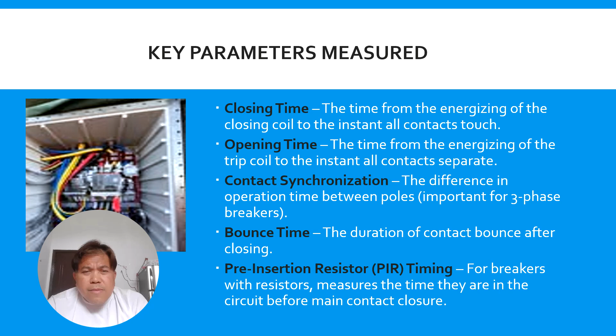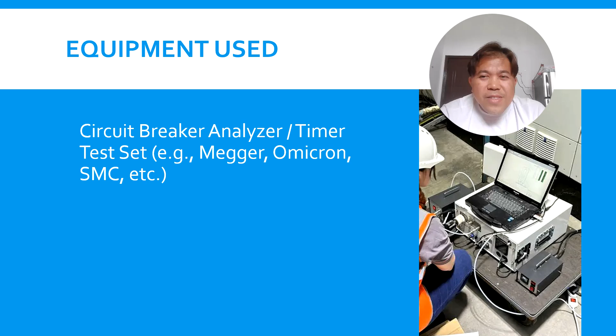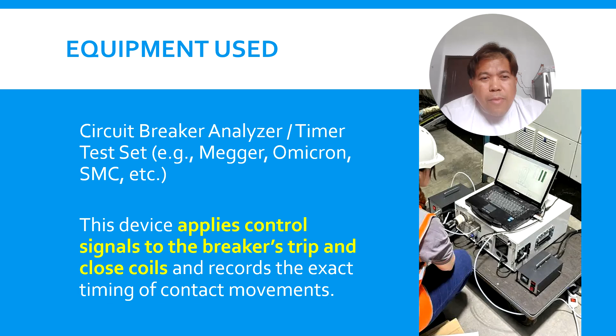Now, the equipment used. What kinds of equipment are we using? It's very simple: a circuit breaker analyzer, a timing test set, a Megger, or maybe you are always using Omicron, which is very popular. So what does the device do? It applies a control signal to your breaker trip and close coils and records the exact timing of the contact movement. That's why we are using this kind of equipment to identify all of our scenarios.